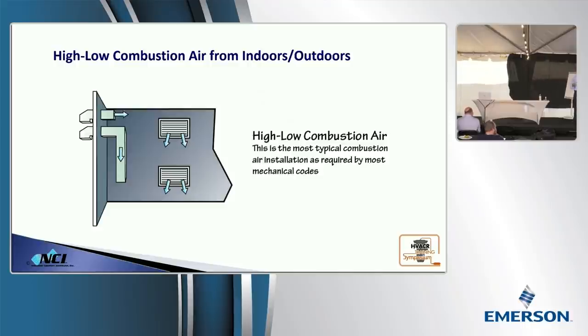What depends on this working? Pressure, because that's the opening. It depends on pressure. Pressure and temperature are what drives flow through those. Depending on which is greater is going to depend on which way the air goes. Typically, you'll see these work about half the time. The other half the time, they're exhausting air.